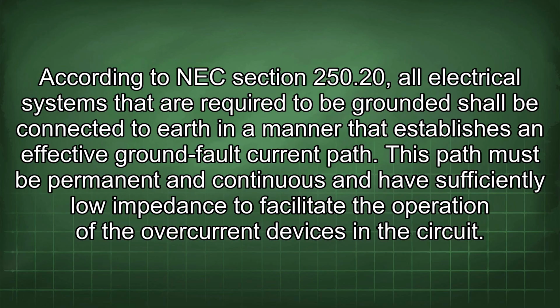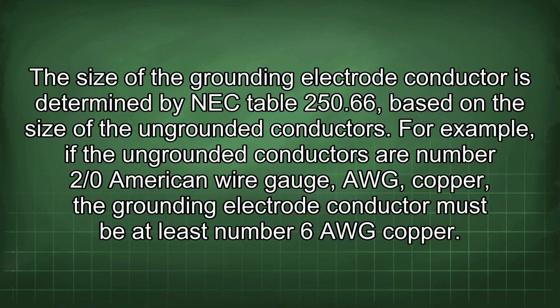According to NEC Section 250.20, all electrical systems that are required to be grounded shall be connected to earth in a manner that establishes an effective ground fault current path. This path must be permanent and continuous and have sufficiently low impedance to facilitate the operation of the overcurrent devices in the circuits. The size of the grounding electrode conductor is determined by NEC Table 250.66 based on the size of the ungrounded conductors. For example, if the ungrounded conductors are number 2/0 American Wire Gauge, AWG, copper, the grounding electrode conductor must be at least number 6 AWG copper.